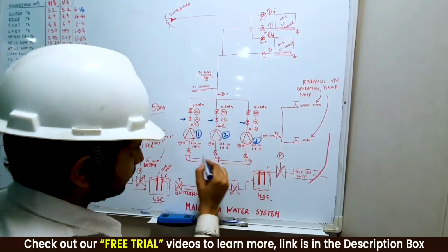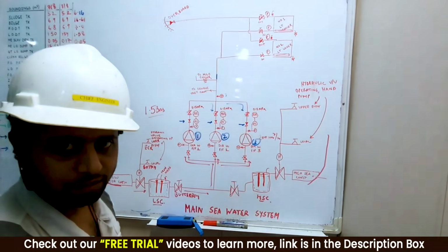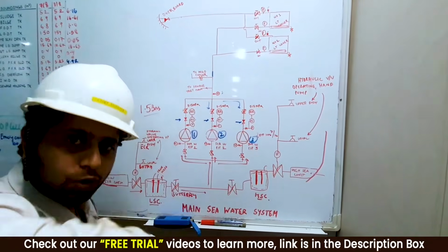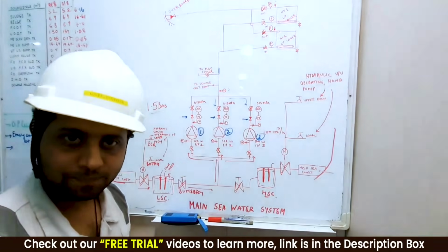Tick, tick. It will also go like this downwards, so very little pressure will be developed over here. The second problem is that your pump is going to rotate in the opposite direction. The motor will turn backwards, and when this happens, there are chances of your mechanical seal getting damaged.